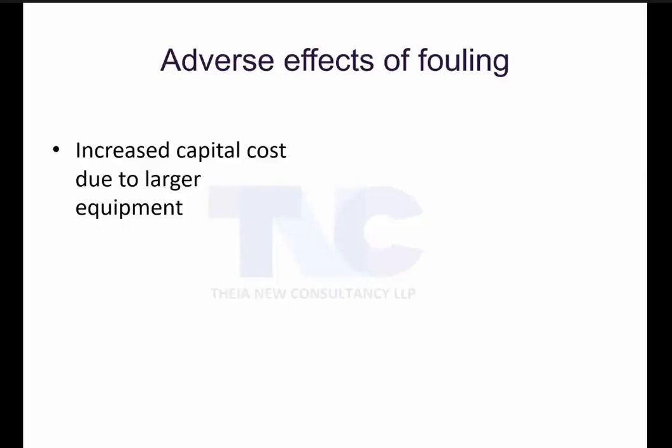So generally what you do is, okay, I have fouling, so you collect the fouling data. I will tell you how to get it. Then you will size a bigger exchanger. Instead of 10 kilowatt, you may size it for 12 kilowatt. Your process requirement is only 10 kilowatt, but because of fouling you are selecting a bigger-area exchanger, because slowly the performance will come down.